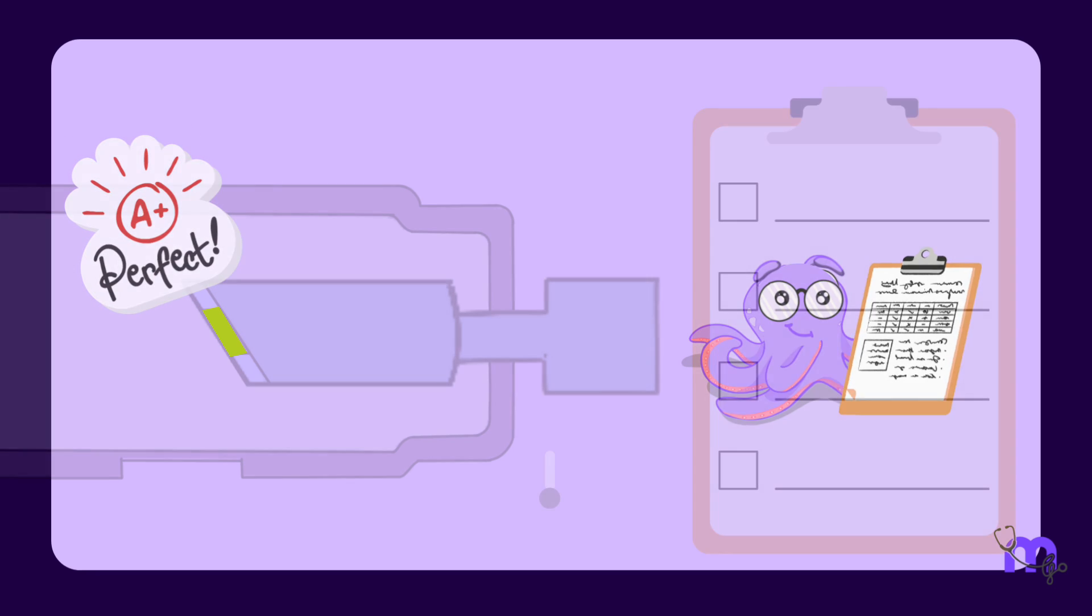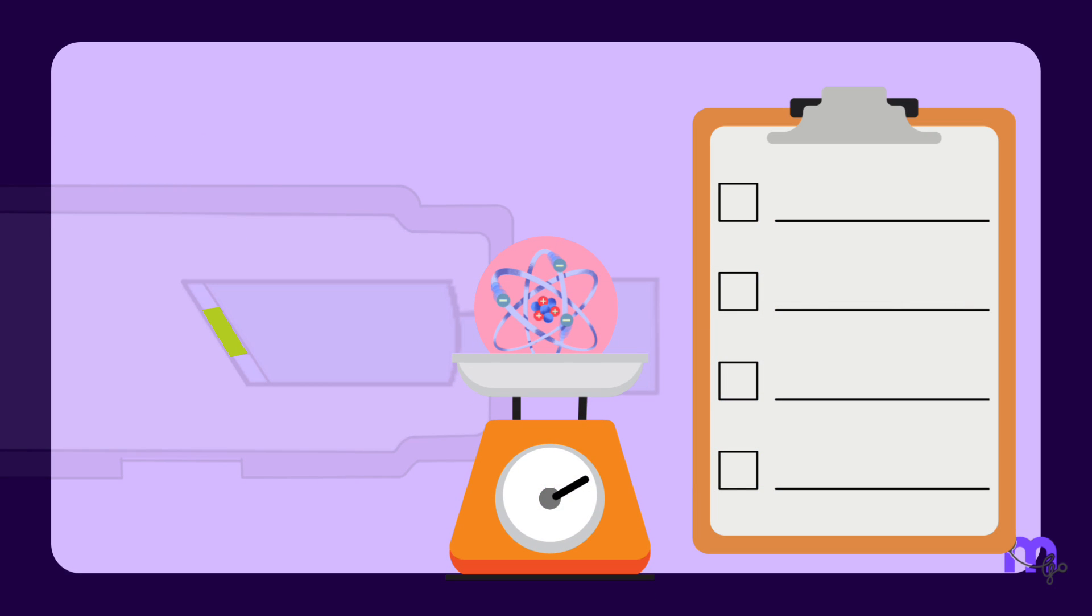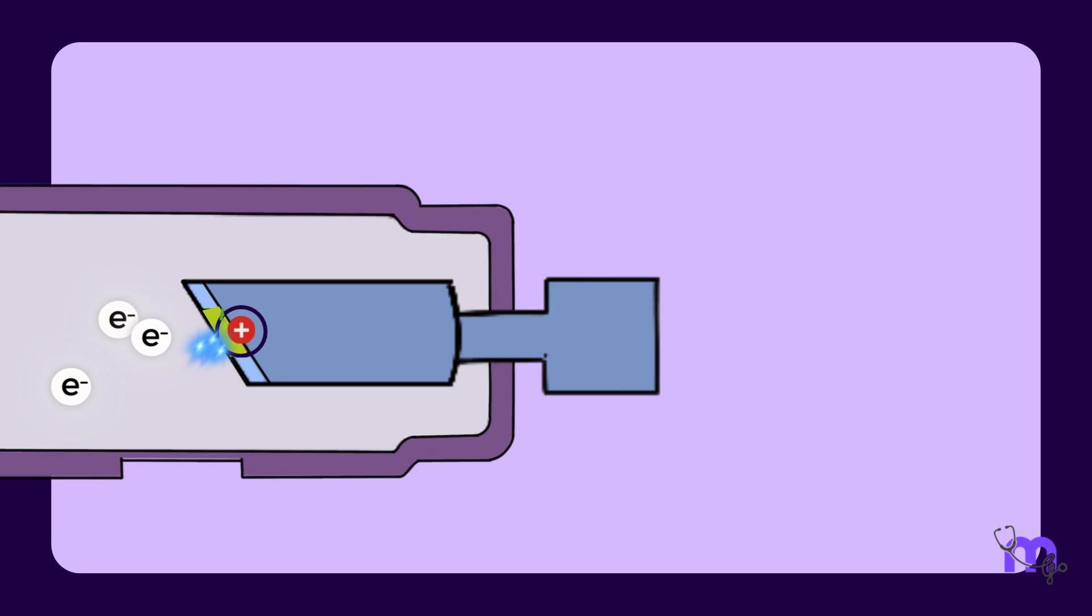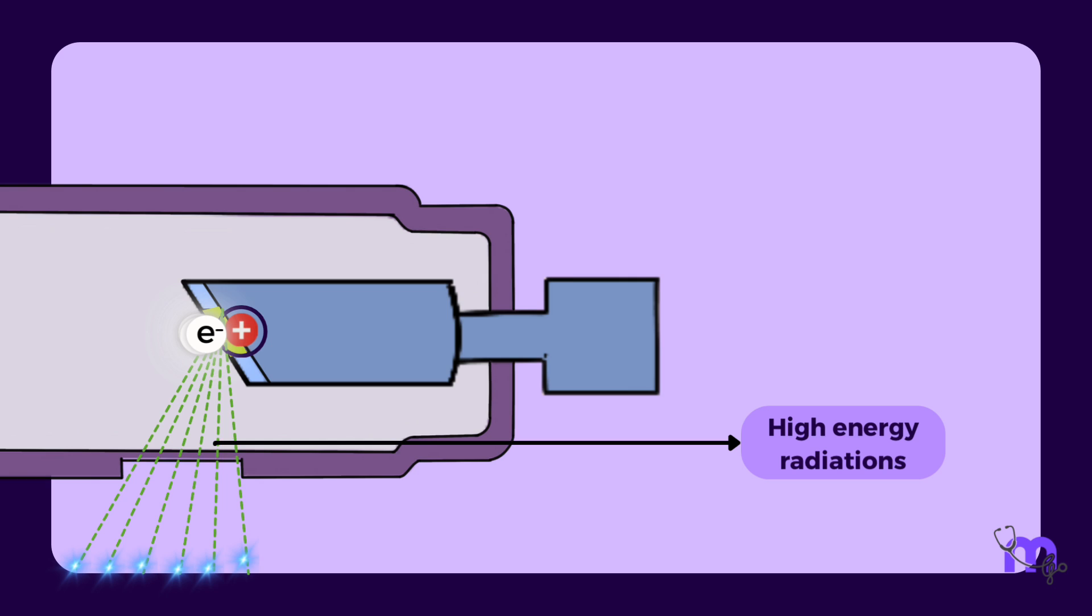It is important to understand that the target has to be made of a material that meets certain criteria to be called ideal. First, the chosen element must have a high atomic number. An elevated atomic number indicates a high concentration of protons within the nucleus, which implies that the nucleus is highly charged. This causes greater deceleration and deflection of the incoming electrons, producing higher energy radiation.